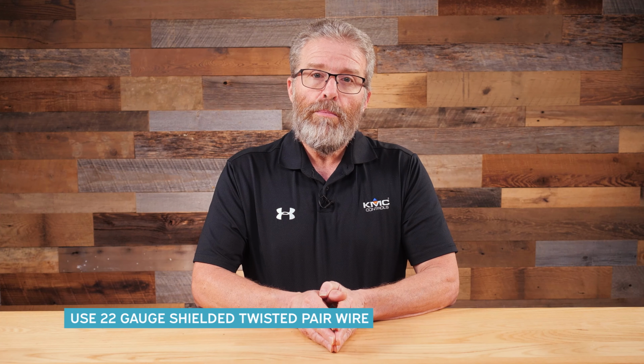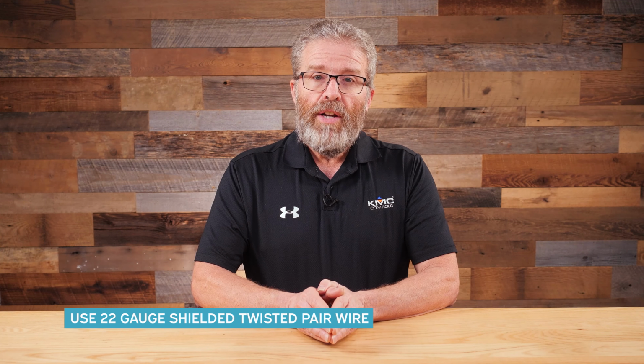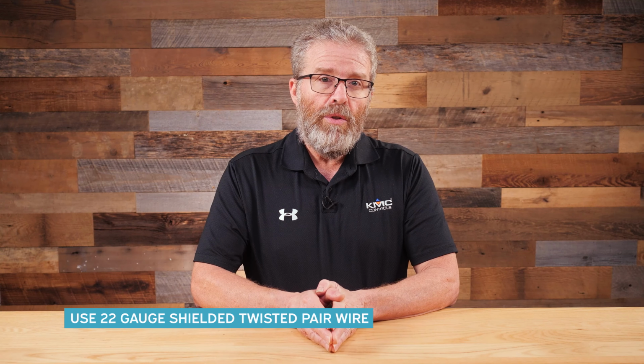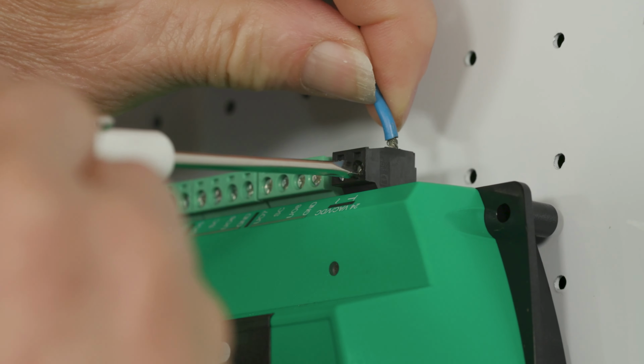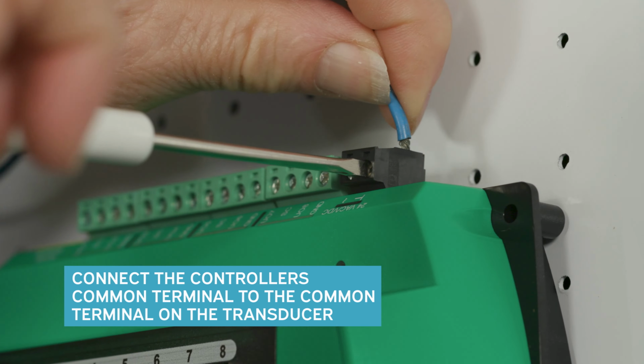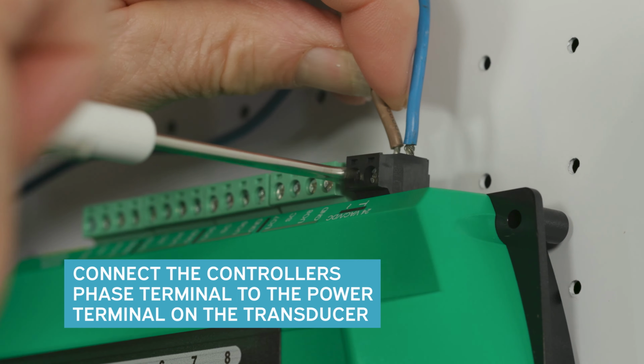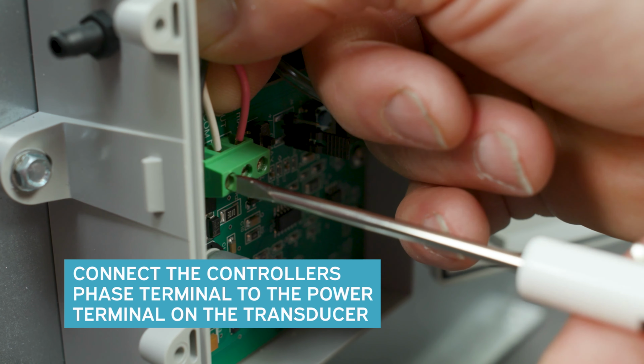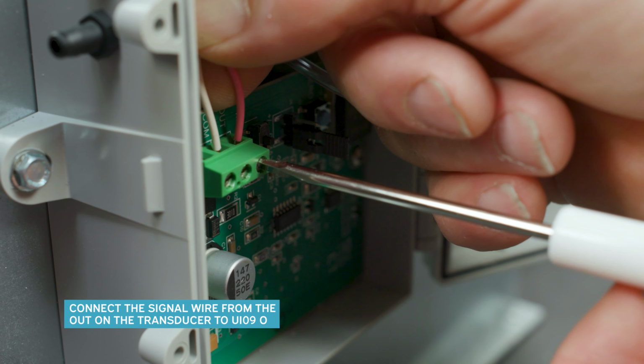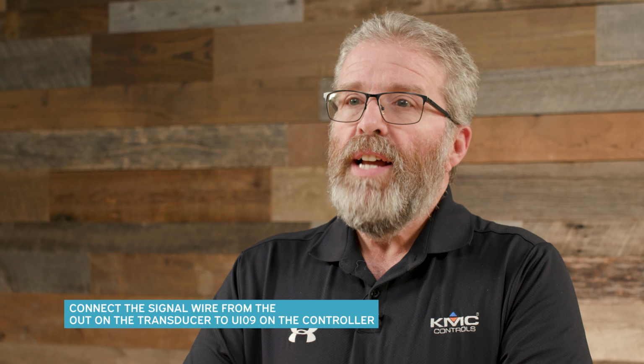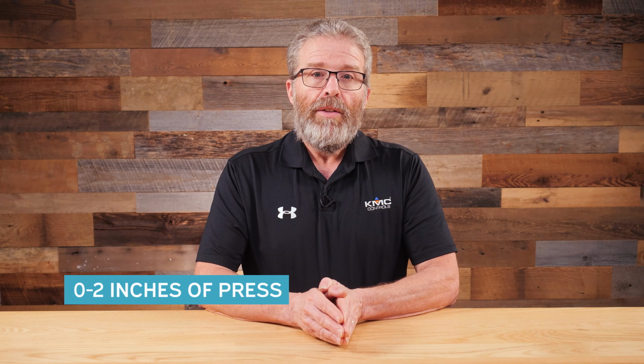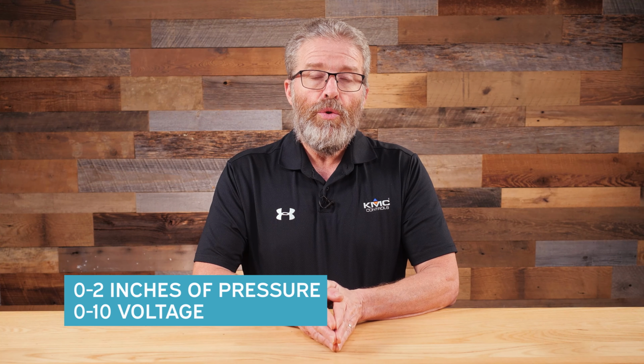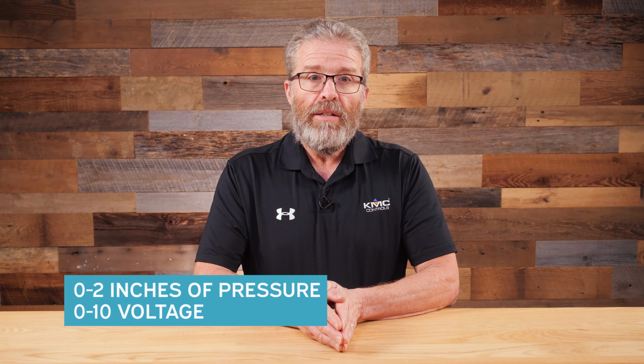To connect the wiring from the transducer to the AFMS controller, use at least 22 gauge shielded twisted pair wire for all your connections. And do not locate this device's wires in the same conduit with wires supplying inductive loads. First, connect the AFMS controller's common terminal to the common terminal on the transducer. Then, connect the AFMS controller's phase terminal to the transducer's power terminal. Lastly, connect the signal wire from the out on the transducer to UI9 on the AFMS controller. The transducer should be set for 0 to 2 inches of pressure and 0 to 10 for the voltage.